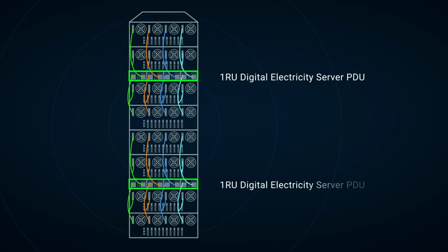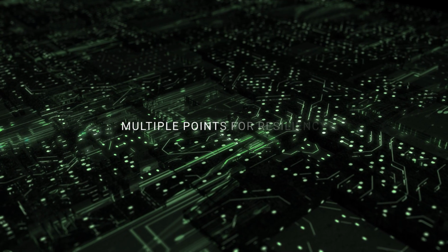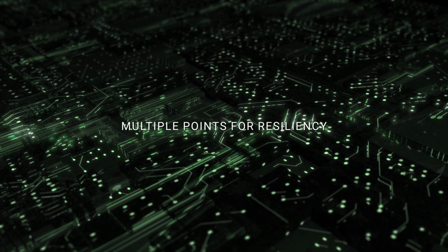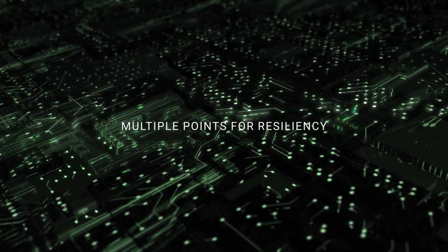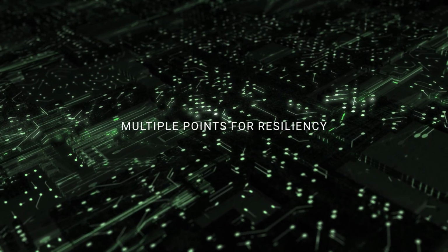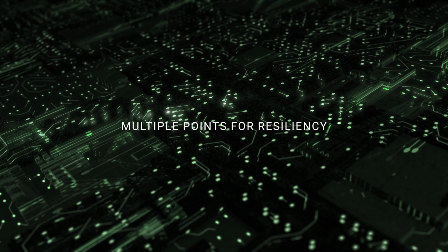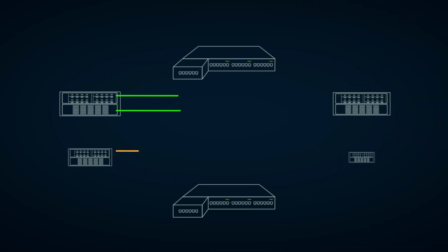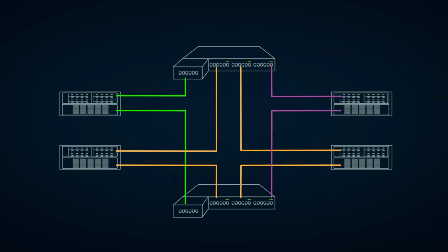This is the look of the deployment inside the server cabinet now, with 2 50-kilowatt server cabinet PDUs in an N+1 configuration. Because VoltServer's digital electricity is an intelligent system with multiple points to increase resiliency, you have the flexibility to easily design your power backup as you see fit. In this image, we're demonstrating 4 redundant transmitters feeding 2 digital electricity PDUs within a server cabinet.